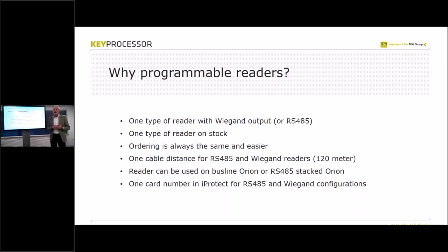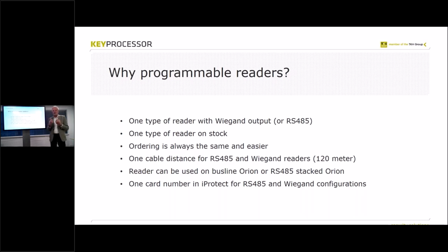You order the readers, and with the configuration card — you'll learn what that is shortly — you can start using the readers. Another benefit is cable distance: RS485 and Wiegand have the same cable distance of up to 120 meters between the Orion and the reader. Standard clock-data as Key Processor normally uses is 50 meters. On a cable bus line using Wiegand or RS485, it's always 120 meters, which is much easier for calculating the system. And it can be used on the bus line or stacked, as already mentioned.